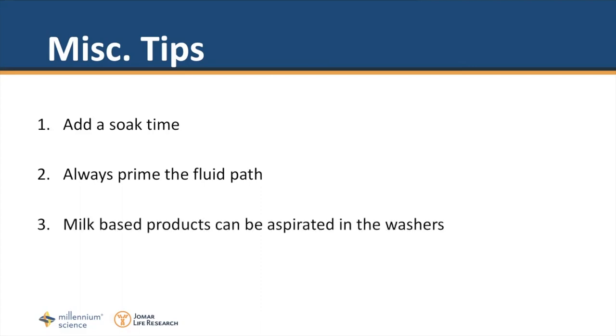Finally yes you can use milk based products or protein rich solutions in the washers. I just recommend using a protease in your maintenance routine.